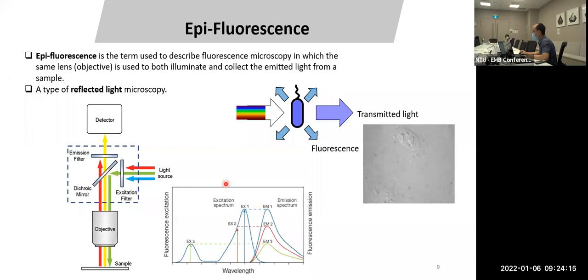And because there's a Stokes shift, the wavelength is now different. It now gets transmitted, right? Because it's above a certain wavelength, the dichroic mirror will transmit the light, and it hits the second filter, which is the emission filter, that further selects the wavelength that you want to collect your light from, and finally the detector. So that's in a nutshell how the basic fluorescent microscope works.